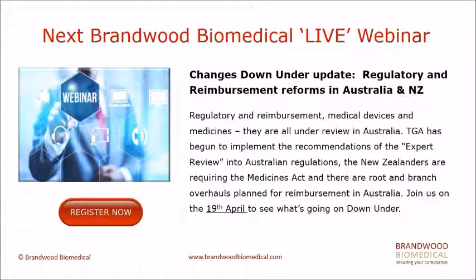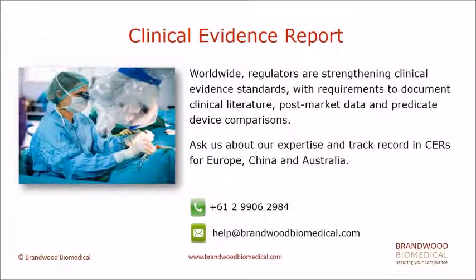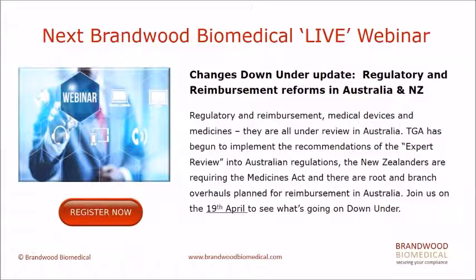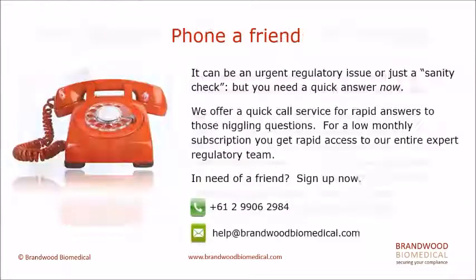If the product registration is expiring and you've got some technical changes, what is the process? Can you actually do those technical changes with your renewal? Okay, so for renewal submissions, the variation application needs to be submitted separately. The renewal submission is mainly an administrative process. It is an application to request extensions on the existing registration. So it is under the assumption of no change to the device since the last approval and all information remaining current.